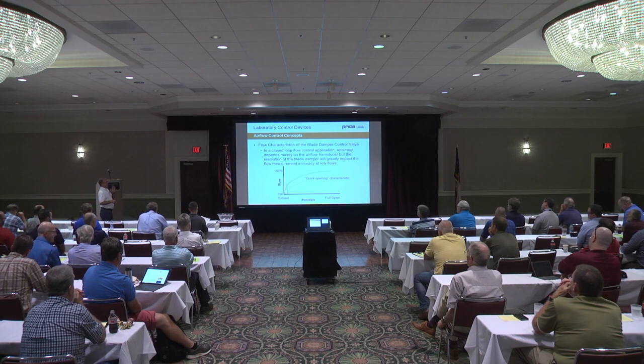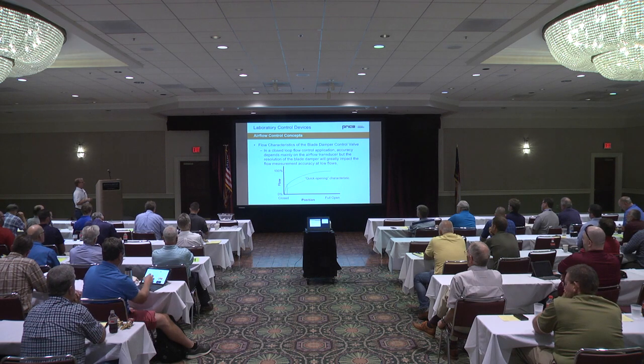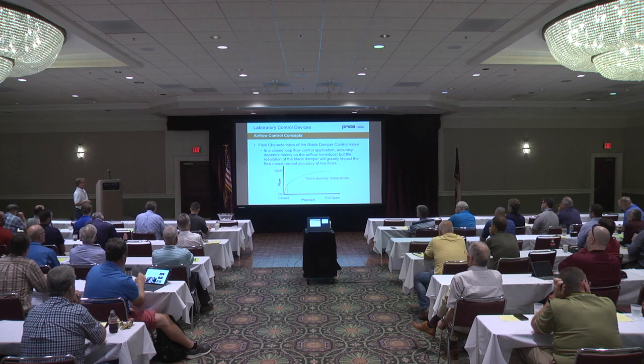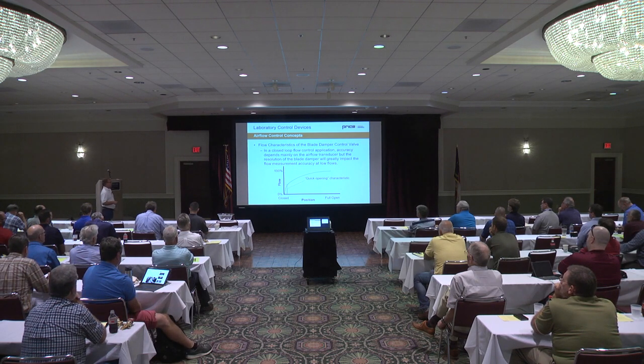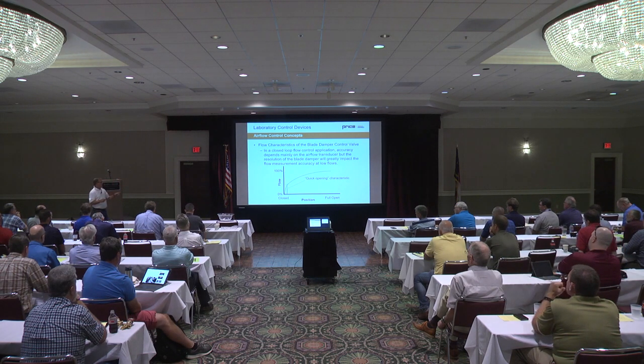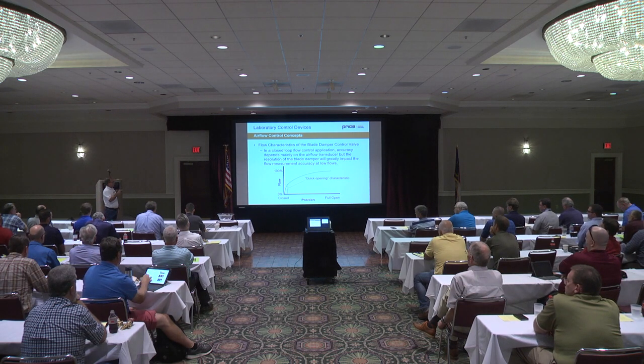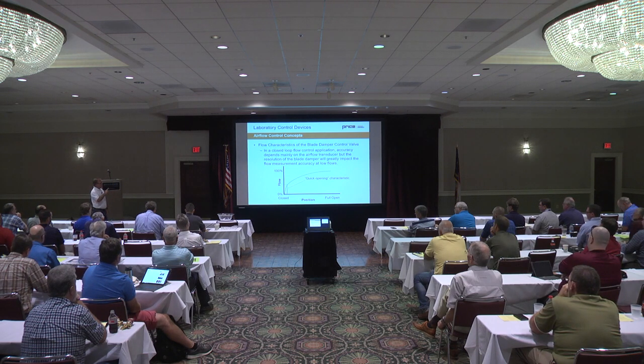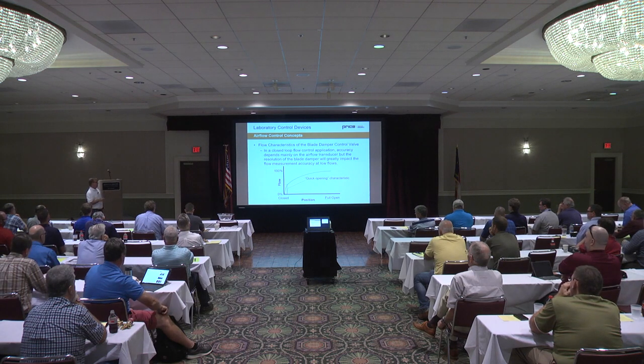So we get into flow characteristics of controlling flow in these different applications. With the blade damper, the flow control application actually depends mainly on the airflow transducer, but the resolution of the blade damper will greatly impact the flow measurement and accuracy at low flows. As we've all seen in air measurement and airflow control on a blade damper, airflow gains really quick at the bottom end. As the damper starts to open, you get a huge amount of your airflow from 0 to probably 25 or 30%, and then the rest of the CFM will come out as you fully open the damper. But it's difficult to control airflow in that small range of opening, from 0% to 10 or 15%, with huge amounts of airflow increase at that point.